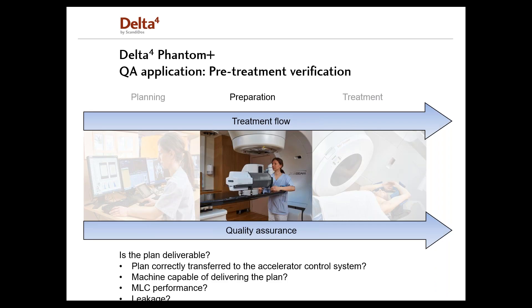ScandiDos offers a family of products covering QA from planning, where we have our secondary planned dose calculation system based on Monte Carlo, the Delta4 TPV, into final fraction, where we have our transmission detector, the Delta4 Discover. For the pre-treatment verification phase, we have the Delta4 Phantom Plus. The questions to be answered here are: is the plan deliverable? Is the plan correctly transferred to the accelerator control system? Is the machine capable of delivering the plan? How is the MLC performance? And is the leakage correctly modeled in the TPS?